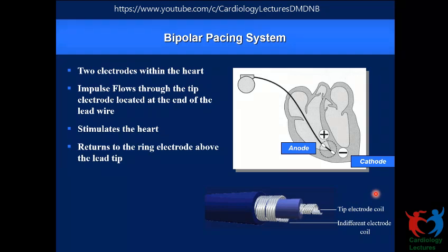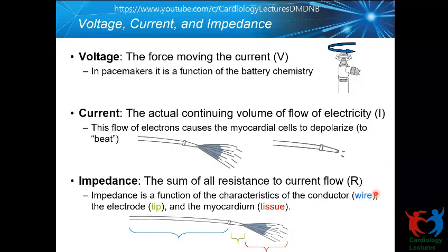And then, yes, we are passing current from the pacemaker, which is derived from the battery. So the battery provides the voltage, which is kind of a force that pushes electrons across the circuitry. And then it is passed through the wire, just like water is passed through the hose pipe in any water hose system. And the water can be imagined as the flow of electrons through this circuit. So the current is the actual measure of the flow of electrons, and this is denoted by the symbol I, and the unit of measurement of current, as you know, is ampere. And in pacemakers we deal with milliamperes. So by increasing the voltage, we can increase the flow of the electrons, just like in a hose from a tank. When you open the tap, it flows more forcefully, let us say.